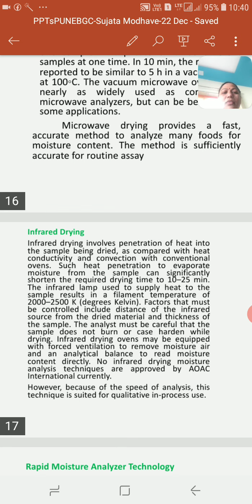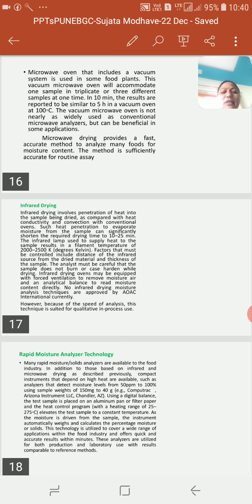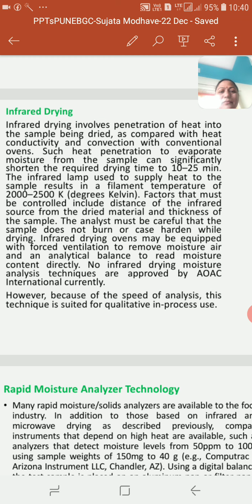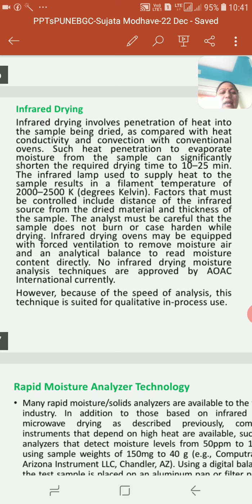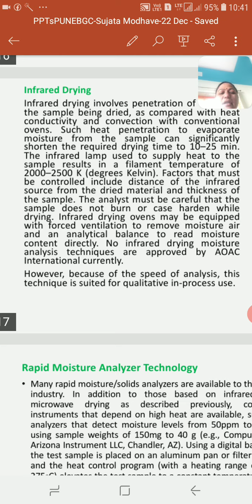Infrared drying involves penetration of heat into the sample being dried, as compared with heat conduction or convection in a conventional oven. Such heat penetration to evaporate moisture from the sample can significantly shorten the required drying time to 10 to 25 minutes. The infrared lamp used to supply the heat results in a filament temperature of 2000 to 2500 Kelvin. Factors that must be controlled include the distance between the infrared lamp and the dried sample. Because of the speed of the analysis, this technique is suitable for qualitative in-process use. So this one is related to infrared drying, where we dry the product with infrared radiation.